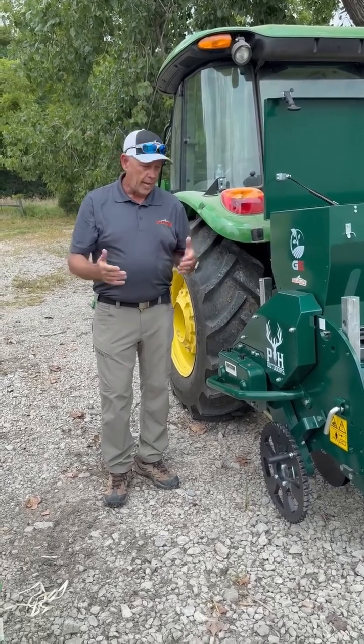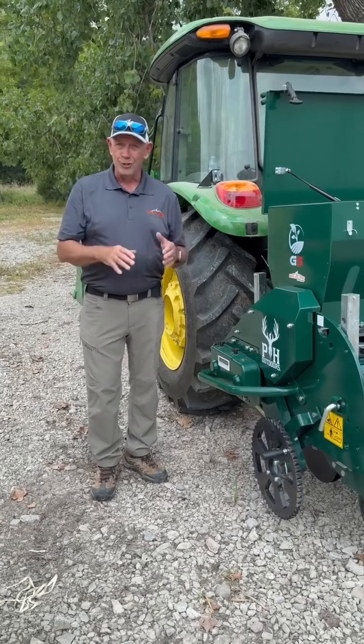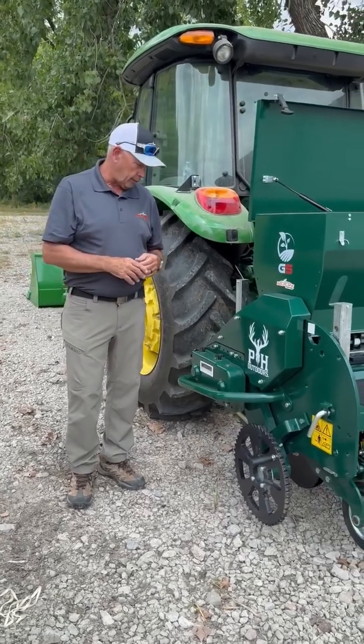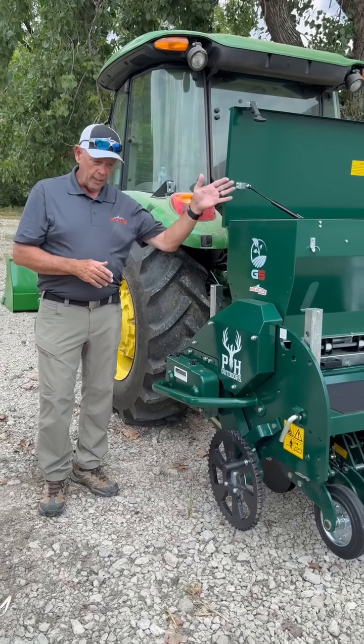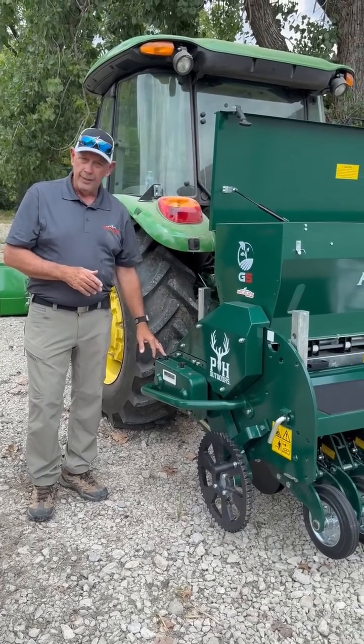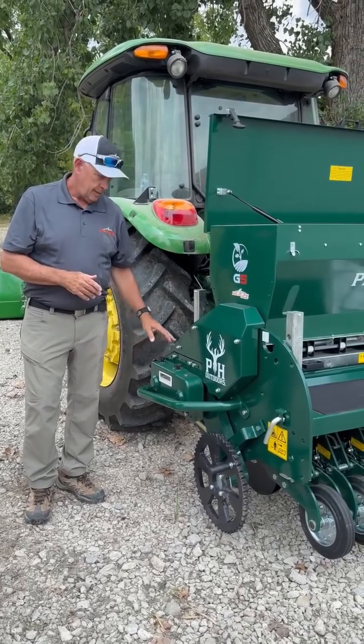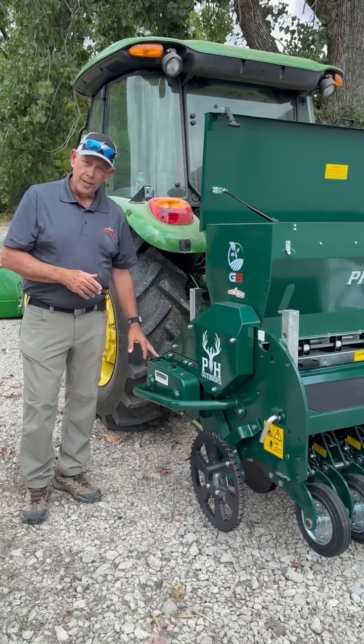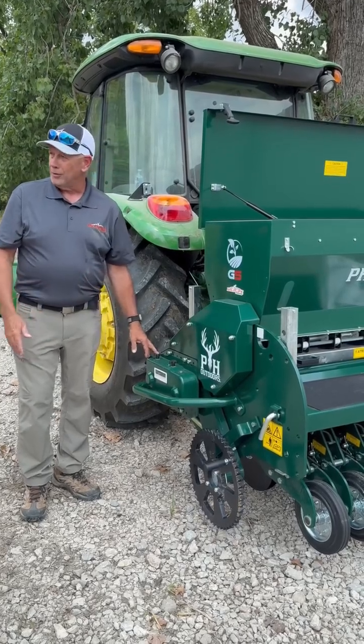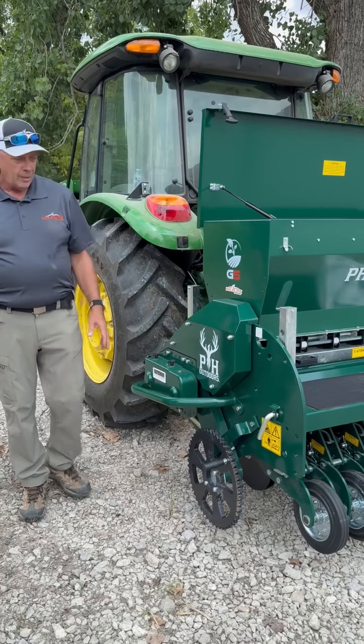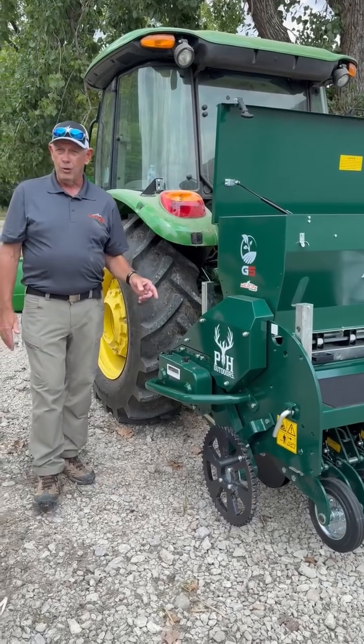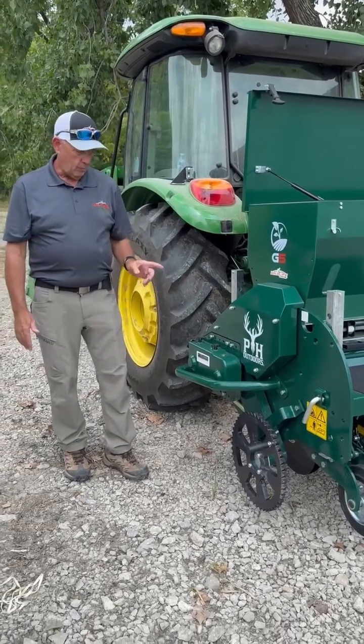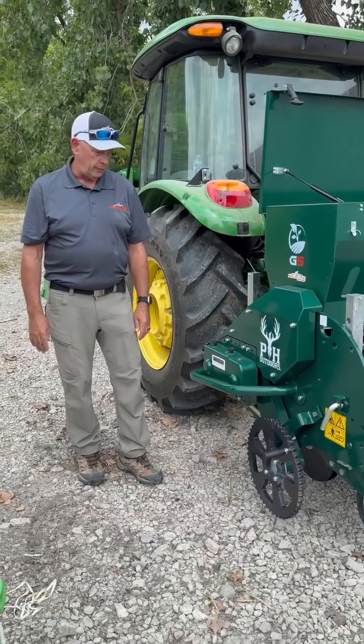So today we looked at the chart. This is just a good starting point; we're still going to calibrate and confirm it. We're at our gate number 2 and gearbox number 3. Number 3 on our gearbox setting gives us like 35.36, and we're looking for 36. We'll run the calibration and see how close we are to that, and then move up or down depending on what we need to do from there.